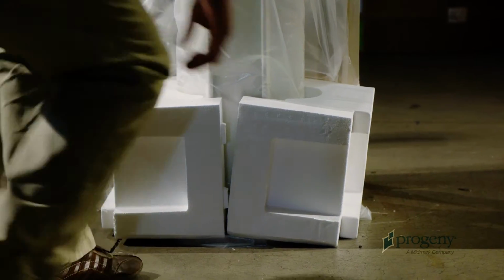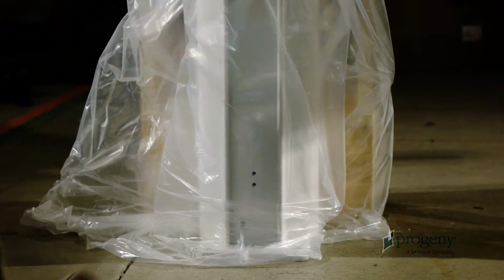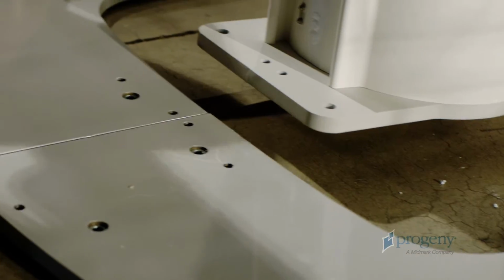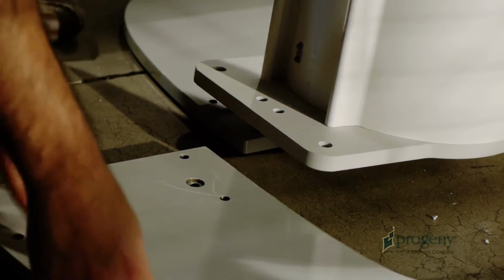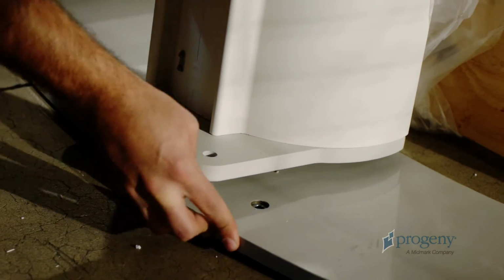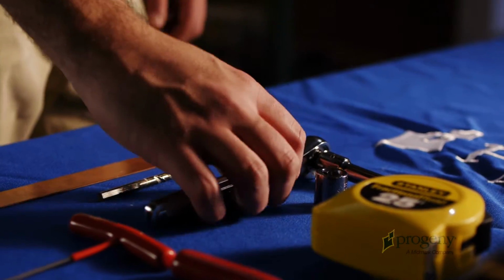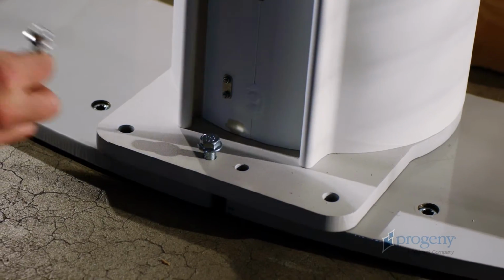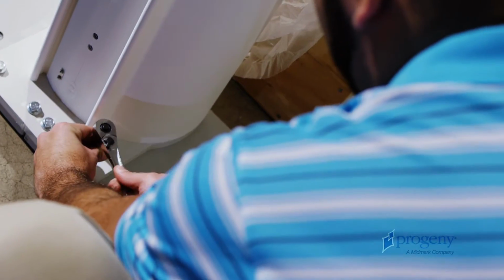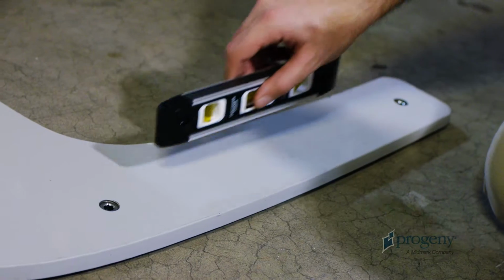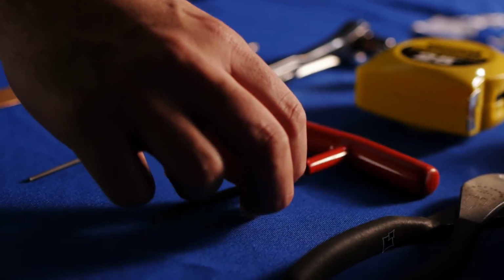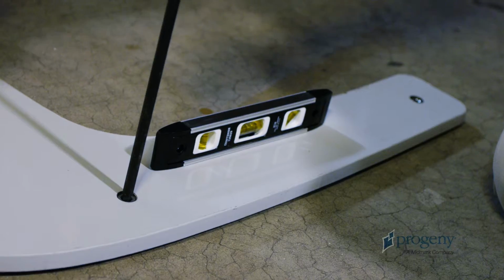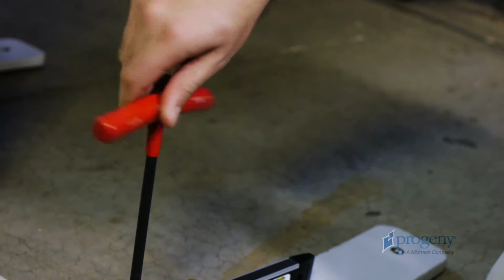If installing using the freestanding base, first remove the packing materials from the base of the column assembly. Carefully tilt the main column forward and slide the freestanding base components underneath. Once properly aligned, use a socket wrench to fasten the outer 4 bolts to secure the column to the base. Be sure to level the base using the adjustment screws. Use an 8mm Allen wrench and turn counterclockwise to adjust the base lower, and clockwise to adjust higher.